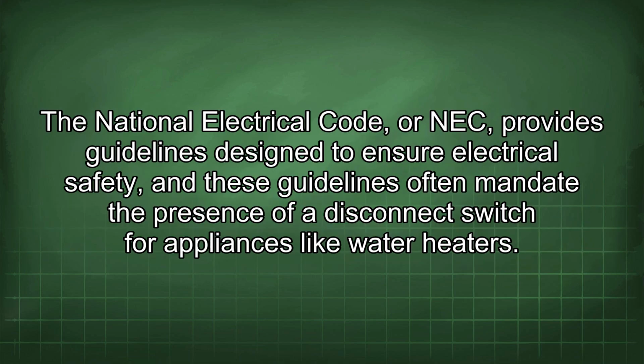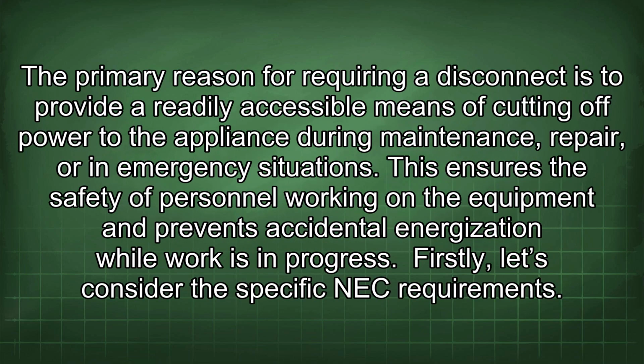The National Electrical Code, or NEC, provides guidelines designed to ensure electrical safety, and these guidelines often mandate the presence of a disconnect switch for appliances like water heaters. The primary reason for requiring a disconnect is to provide a readily accessible means of cutting off power to the appliance during maintenance, repair, or in emergency situations. This ensures the safety of personnel working on the equipment and prevents accidental energization while work is in progress.